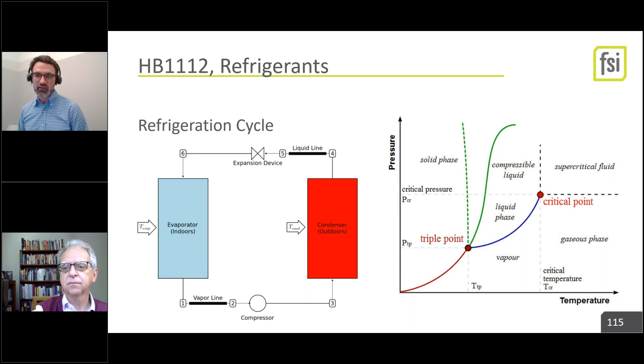R410A is great. We have good equipment. This is indexed against R410A. So you either give up efficiency or you give up volume, so your compressors get weirder and weirder, or you move from non-flammable to slightly flammable. The orange dots are highly flammable, the red triangles. So our most likely heir apparents for refrigerants are R32, which code doesn't really recognize yet as lightly flammable. We don't have a distinction between lightly flammable and really combustible gas.